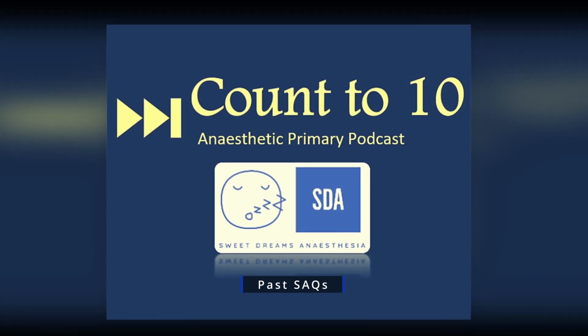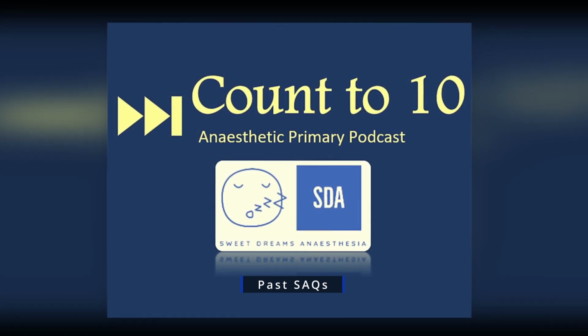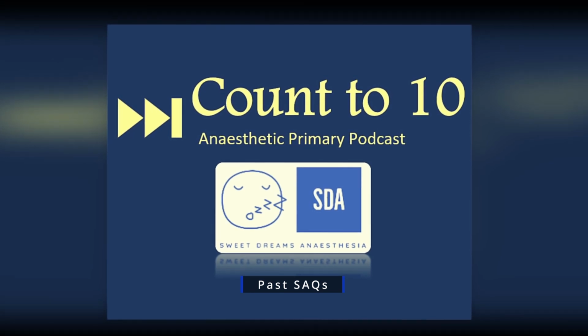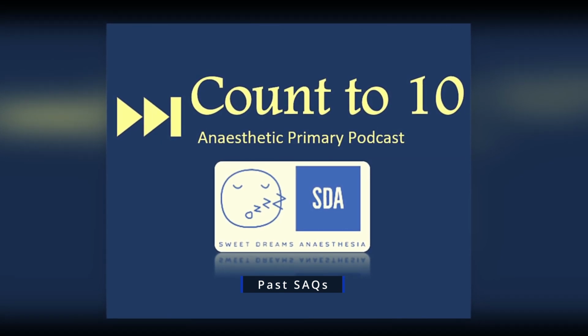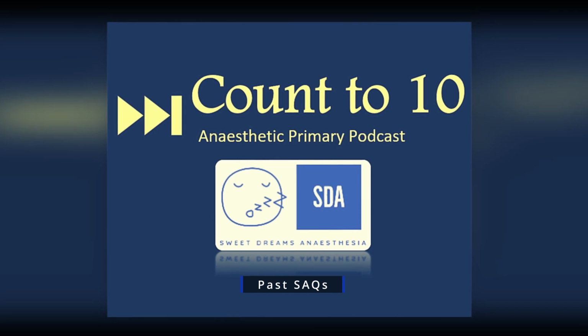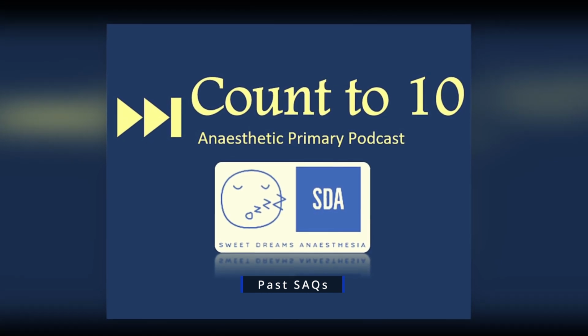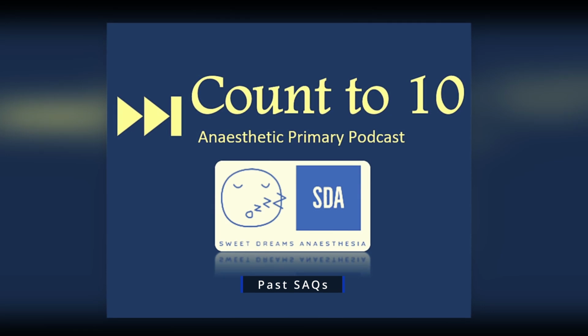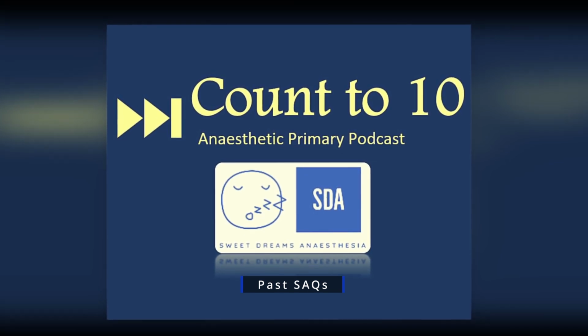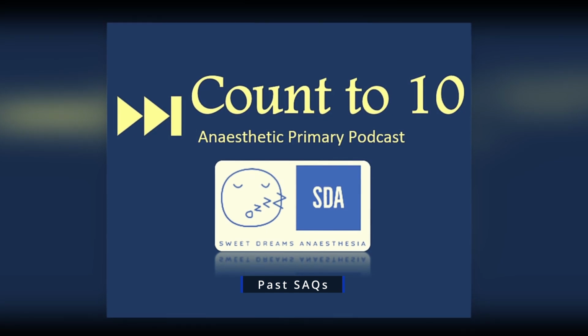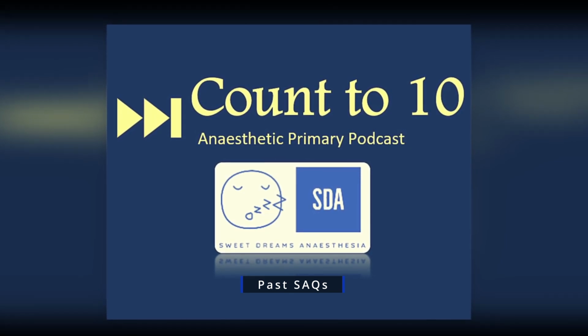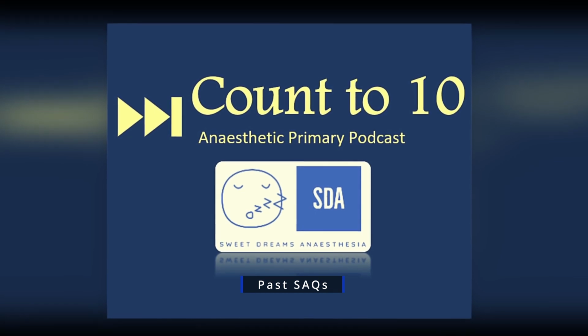Then the errors with the machine itself is that the diastolic blood pressure is the least accurate measurement, followed by the systolic, and the most accurate is the mean arterial blood pressure. The other error with this machine is that at extremes of blood pressure, so too high and too low, it tends to be less accurate, and you can observe this in clinical practice. When you get that blood pressure that can't record because a patient's systolic is 220, it just comes up with dash dash and no output value.